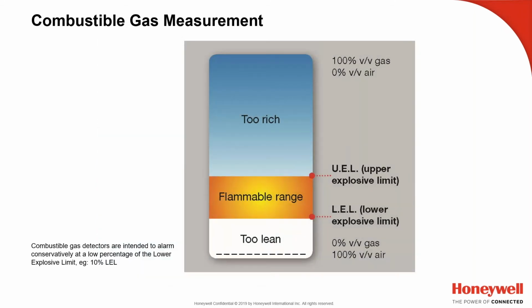But when you're testing for combustible gases, we test in terms of percent LEL. So, for example, 5% methane in air is the lower explosive limit of methane. Below 5%, it's too lean to burn. Above 5%, it will be optimal until it gets to a point where it's above 15%. Then it's displaced enough oxygen that it's too rich to burn. So you have that opportunity between 5 and 15% for methane or natural gas to be combustible.